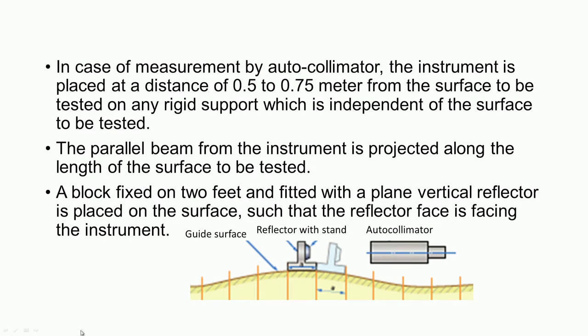When taking readings, the autocollimator should be kept at a distance of about half a meter to 0.75 meter from the surface to be tested. It is placed on a separate stand — not on the surface being tested. The parallel beam from the instrument is projected along the length of the surface. Here, this is the guide surface whose straightness is to be checked, and we mark different positions where we keep the reflector with the stand on the guide surface. Readings are taken through the eyepiece.